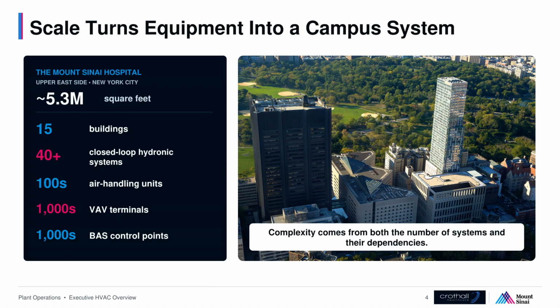The utility spend makes more sense when we look at the campus scale. The Mount Sinai Hospital campus, shown here, is about 5.3 million square feet across 15 buildings. It includes more than 40 closed hydronic systems, hundreds of air handling units, thousands of VAV terminals, and thousands of BAS control points. The complexity is not just the number of components, it is the number of dependencies. A single sequence, valve, sensor, or pump can affect many rooms. The reverse is also true. A verified improvement can be repeated across a large portfolio. Scale multiplies both operational risk and energy opportunity.